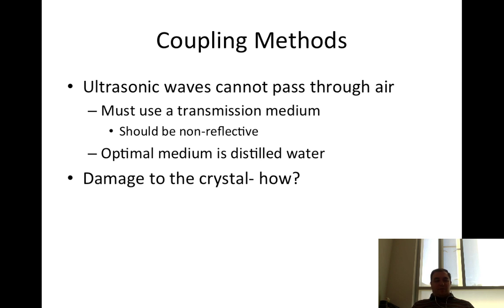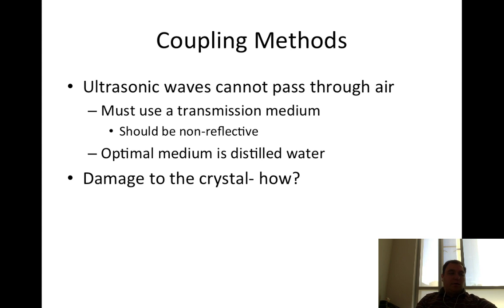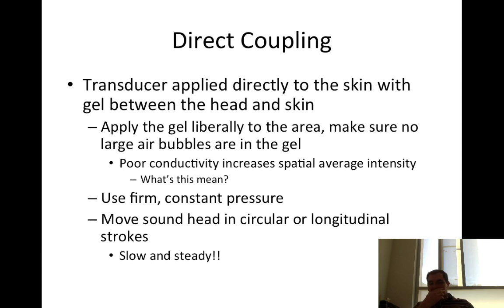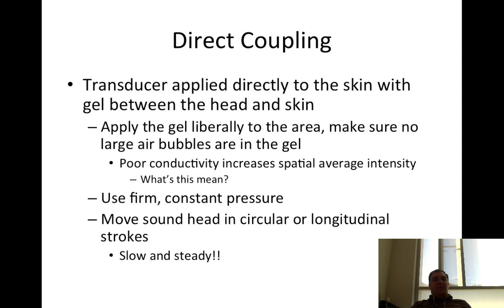You can actually damage the crystal if you hold the ultrasound in the air, turn it on high, and let it reflect and refract. With direct coupling, the transducer is applied directly to the skin with gel between the head and skin. Apply the gel liberally, make sure large air bubbles are out, and always use more gel than you think. People with drier skin will absorb the gel quickly, so don't be afraid to add more as you go.